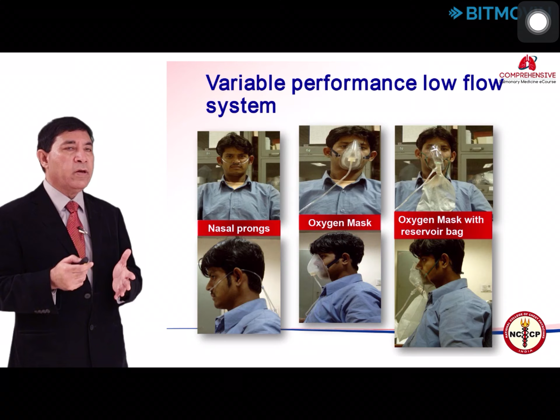The important thing here is that with a nasal cannula you can provide an FiO2 between 0.24 to 0.36. With the mask you can go up to 0.5, and when you need an FiO2 higher than 0.5, then it is important to use a mask with a reservoir. In the reservoir you have two varieties, as I mentioned. With the rebreathing valve, the FiO2 can go up to 0.7 to 0.8, and if you are using a non-rebreathing valve, the FiO2 can go up to 0.9.